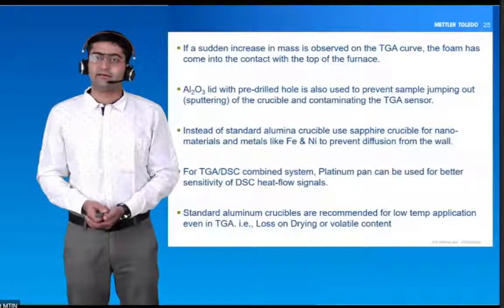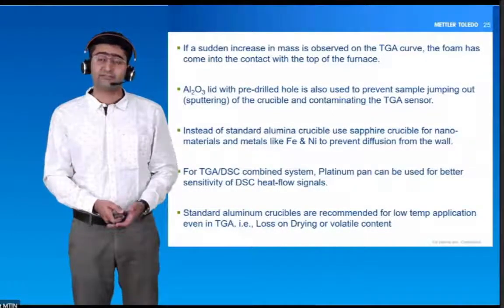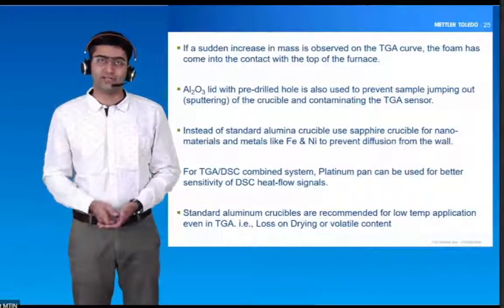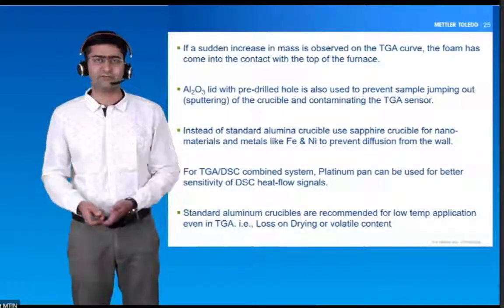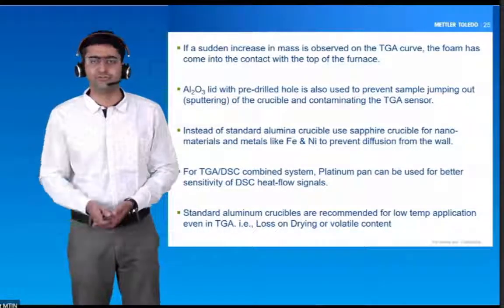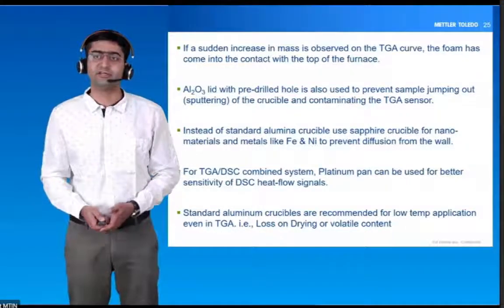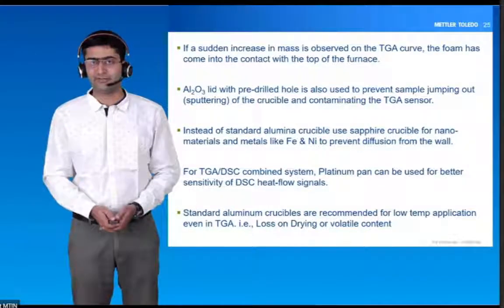For low temperature applications, such as when you want to understand loss on drying or volatile content, instead of a ceramic crucible, you can also use standard aluminum crucibles.